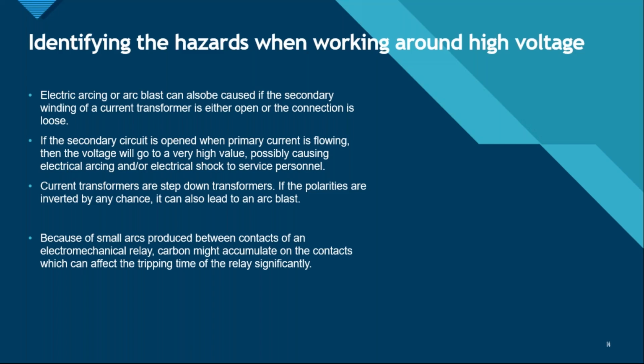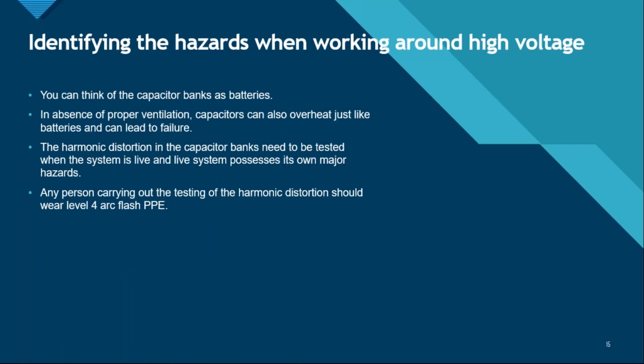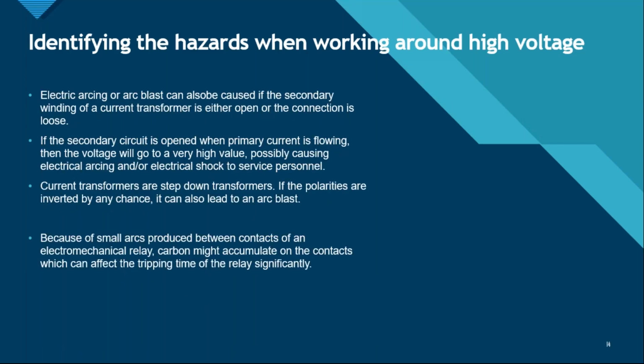If that carbon is not cleaned up, if those relays are not maintained regularly, it might affect the tripping time of the relay, and it might also lead to a huge disaster. It can lead to high current passing through the circuit and might damage all of the equipment connected to that circuit. That's why it's always better to transition to an electronic relay or a numerical relay.